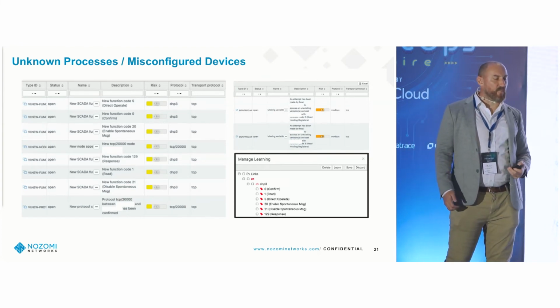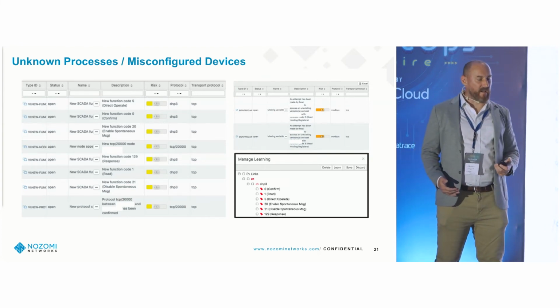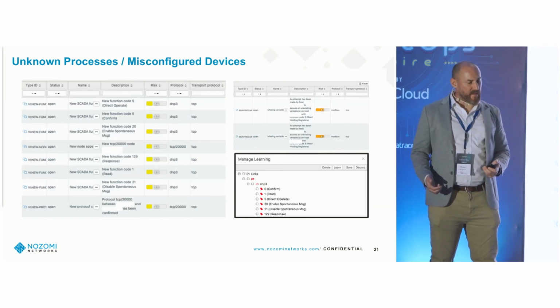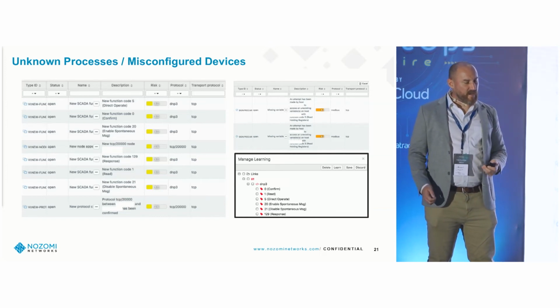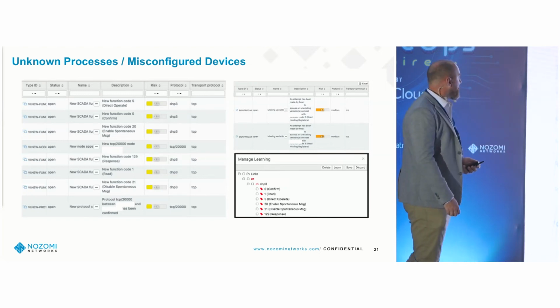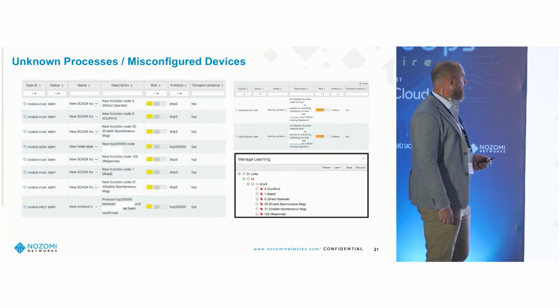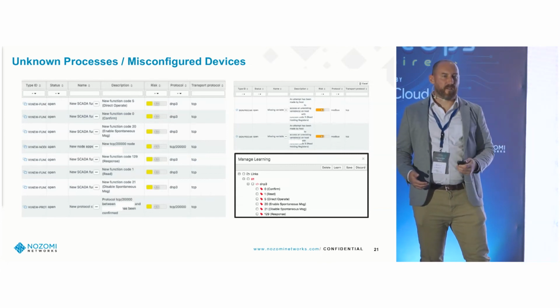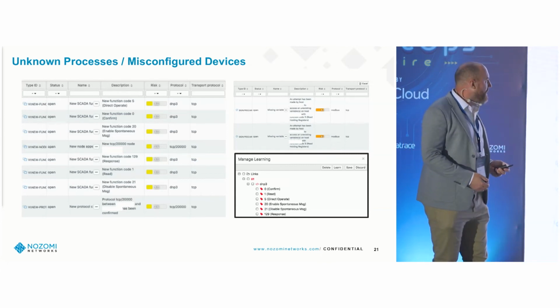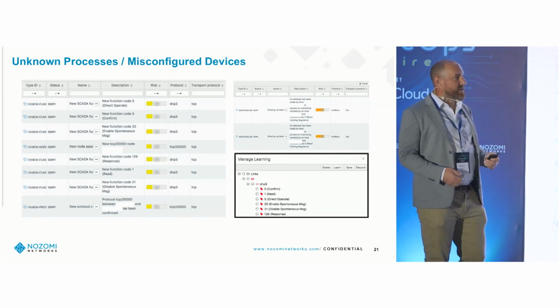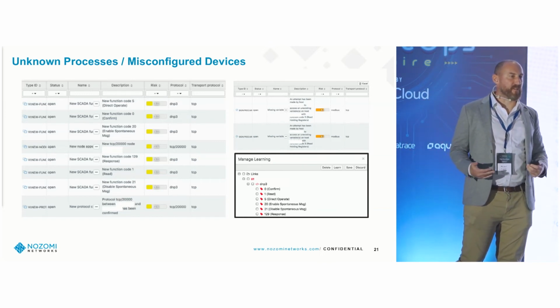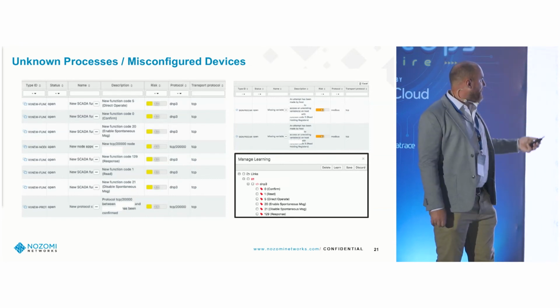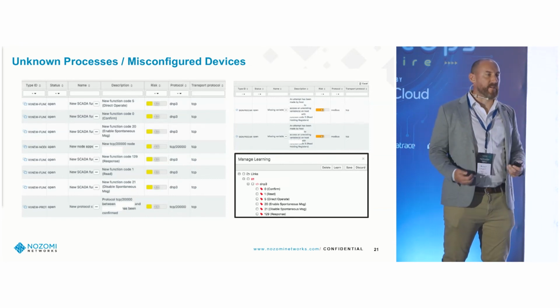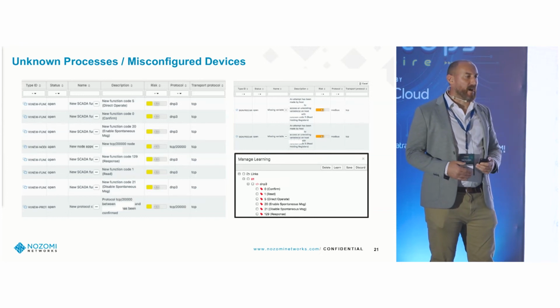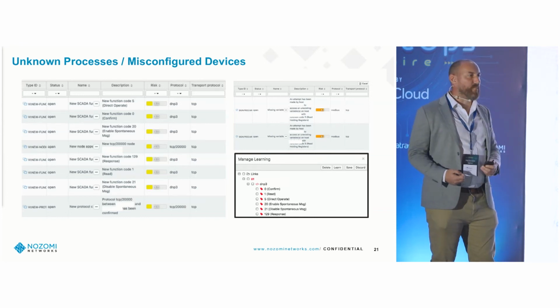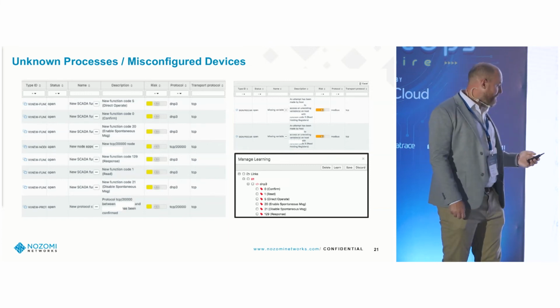Unknown processes or misconfigured devices. This is a screenshot from an implementation, I believe in a hydro generation facility. We see a bunch of new function codes for one of the existing protocols they're using. DNP3 is a very common protocol for industrial communications within substations, but it's not something where you'd typically see a wide range of function codes—you'll have something specific being used for that process. In this case we see a scan of function codes, which could be indicative of a misconfigured device, or it could be indicative of an attacker in the network trying to understand what processes are available to them.